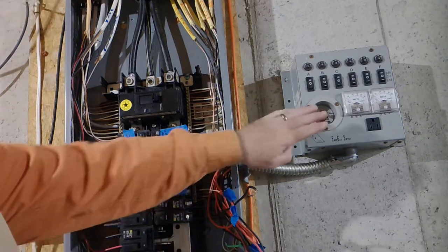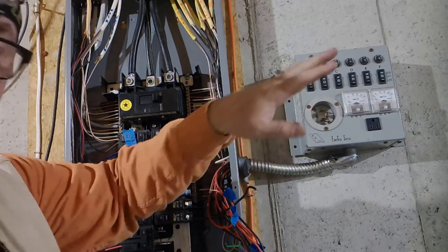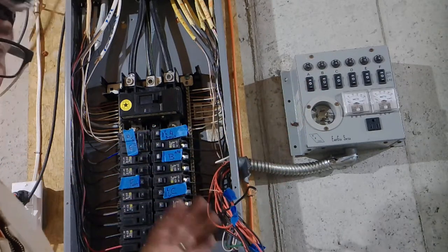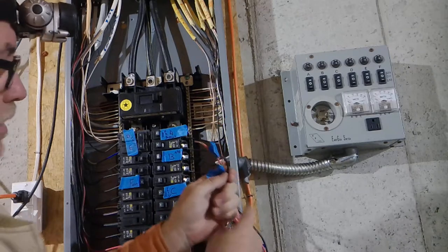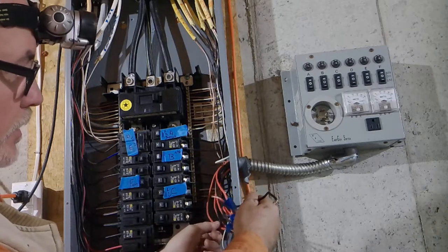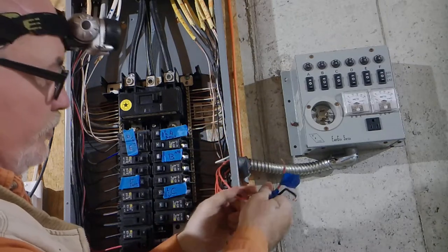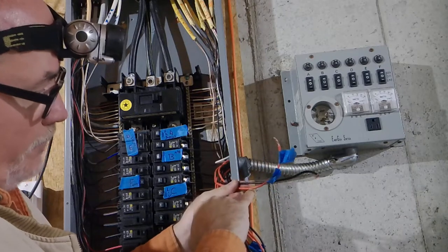Today we're going to wire up this transfer switch. Very simple procedure to do. A couple things you've got to realize. You've got red and black wires. You've got to match up your wires. On these transfer switches, usually the wires are labeled.